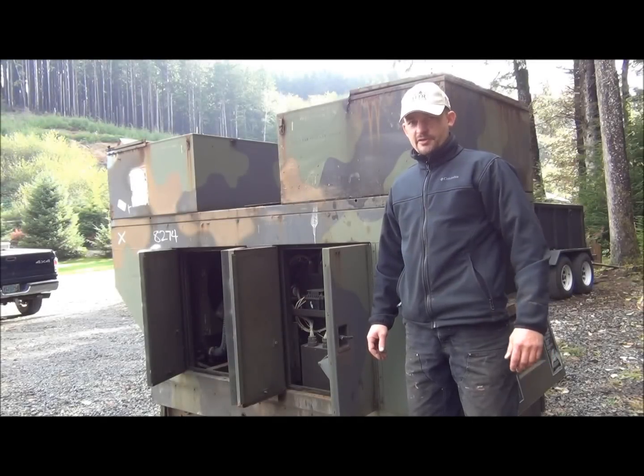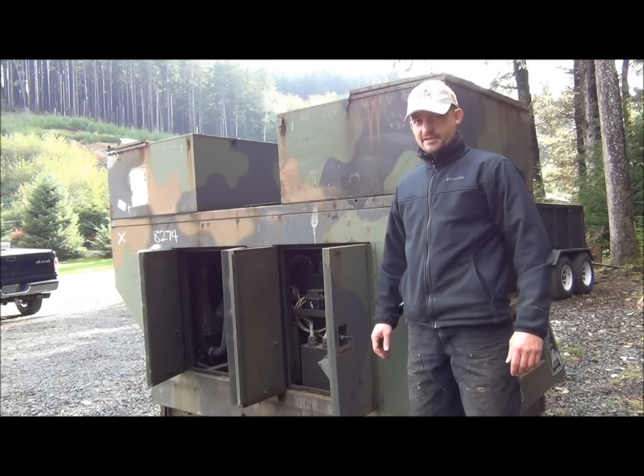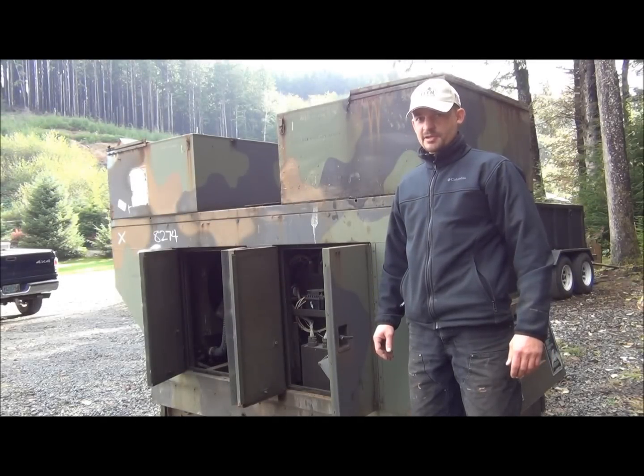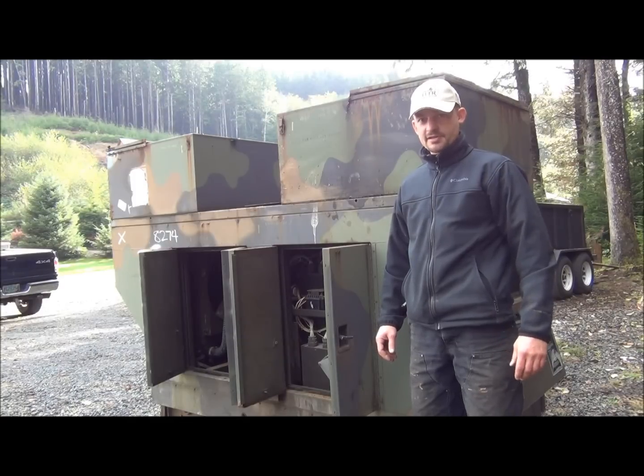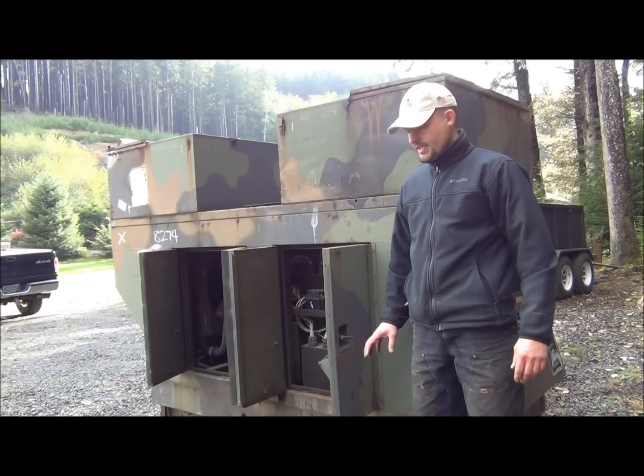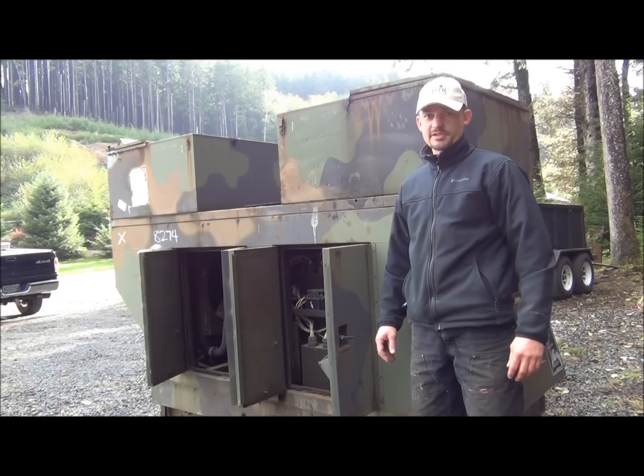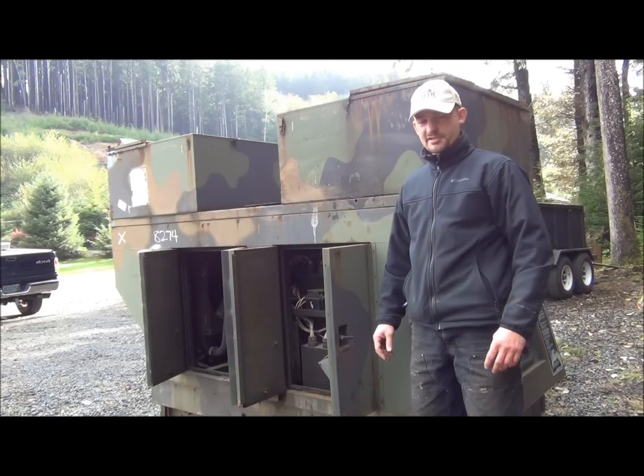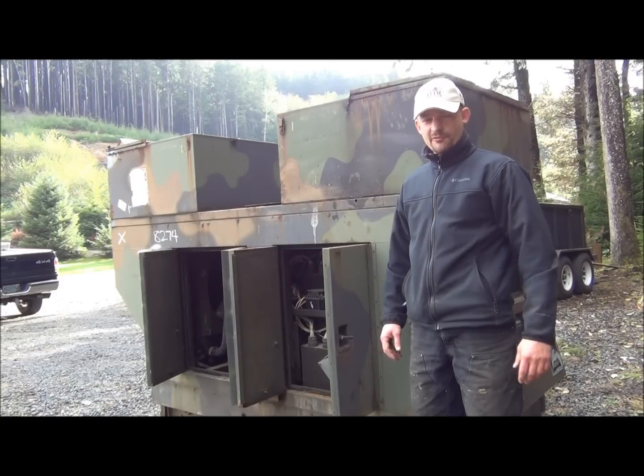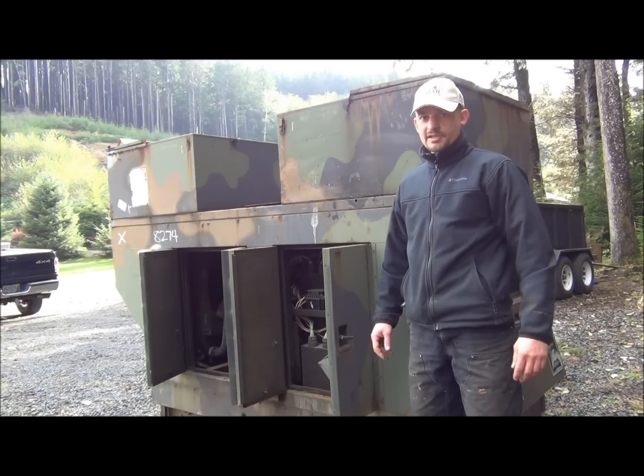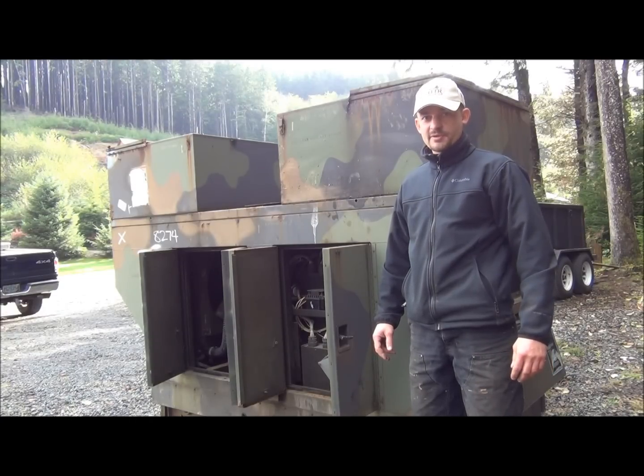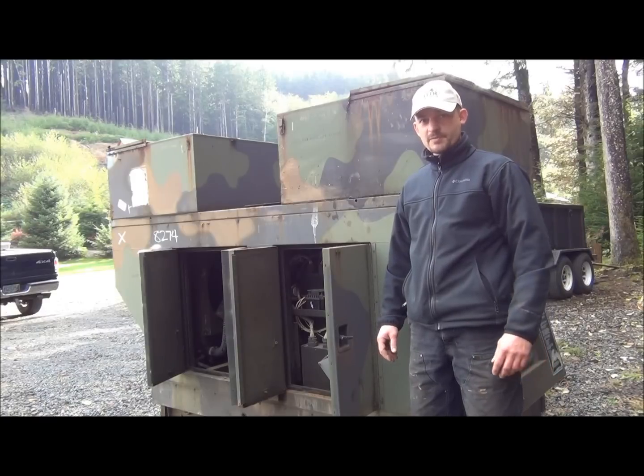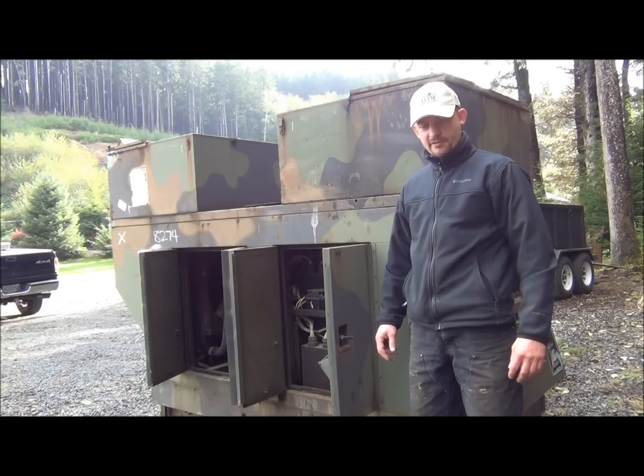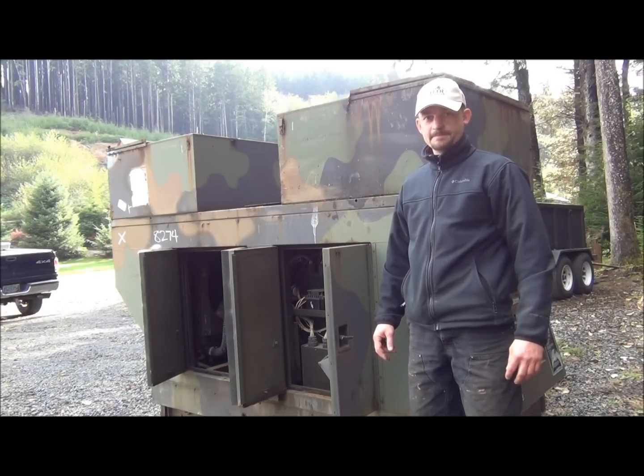Alright, as you can see in the video, the voltmeter agreed almost exactly with the generator's meter, but the frequency meter was way off. The generator I had set to exactly 60 hertz on its built-in frequency meter, and as you can see on the digital frequency meter, we were almost at 66 hertz. So that's more than likely why the overvoltage trip is occurring. The generator is simply turning way too fast. So what I need to do is just adjust the frequency meter, and we can get the generator turning at the proper RPM. And I'm betting that that'll take care of our overvoltage trip on the startup.